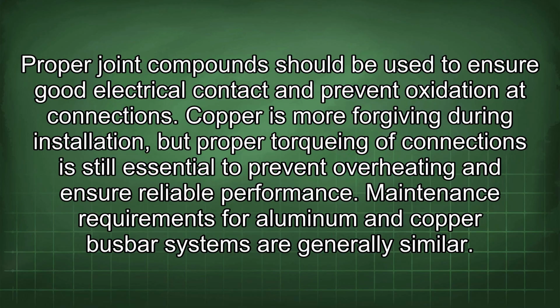Proper joint compound should be used to ensure good electrical contact and prevent oxidation at connections. Copper is more forgiving during installation, but proper torquing of connections is still essential to prevent overheating and ensure reliable performance. Maintenance requirements for aluminum and copper busbar systems are generally similar.